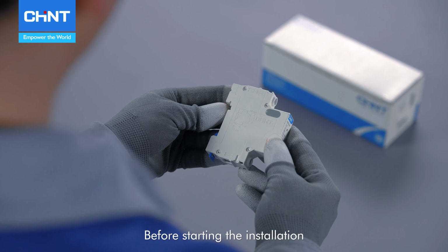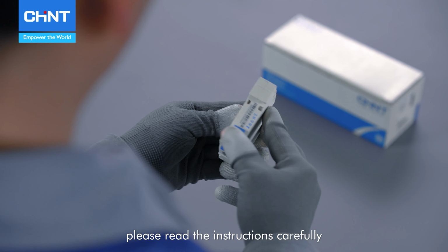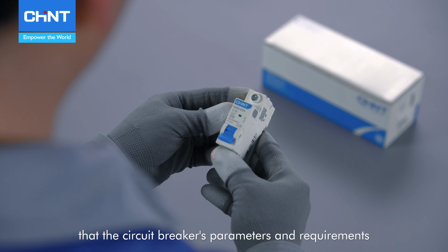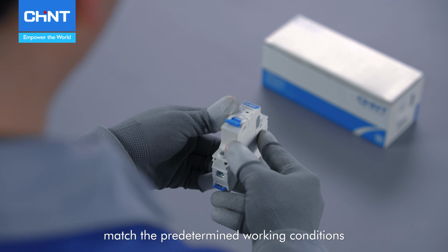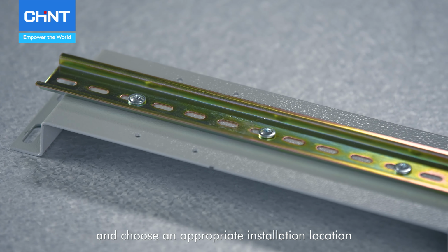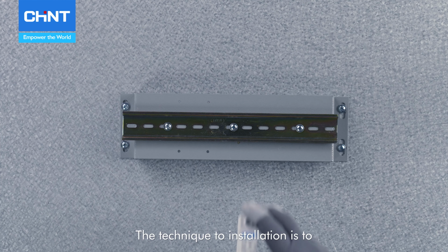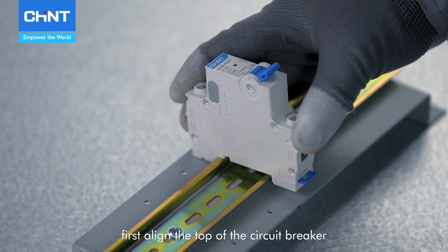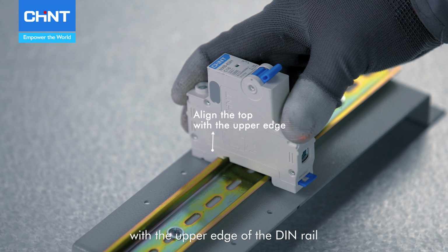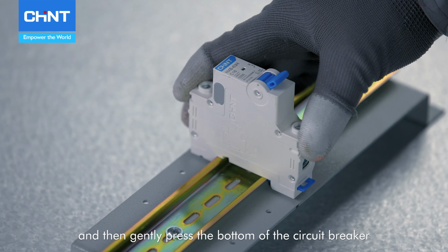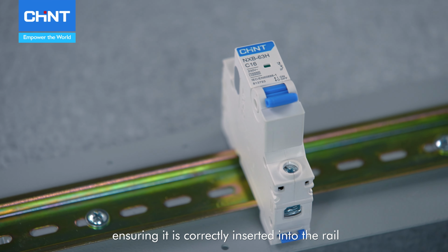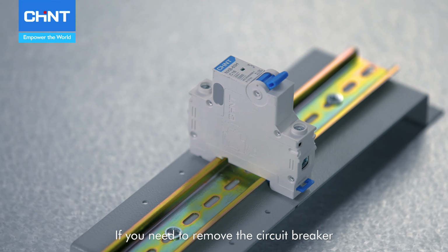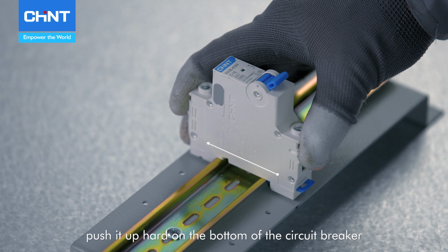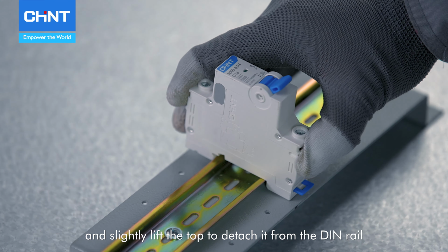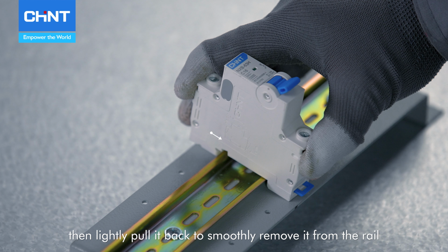Before starting the installation, please read the instructions carefully. Make sure to check that the circuit breaker's parameters and requirements match the predetermined working conditions, and choose an appropriate installation location. The technique to installation is to first align the top of the circuit breaker with the upper edge of the DIN rail, and then gently press the bottom of the circuit breaker, ensuring it is correctly inserted into the rail. If you need to remove the circuit breaker, push up hard on the bottom of the circuit breaker and slightly lift the top to detach it from the DIN rail, then lightly pull it back to smoothly remove it from the rail.